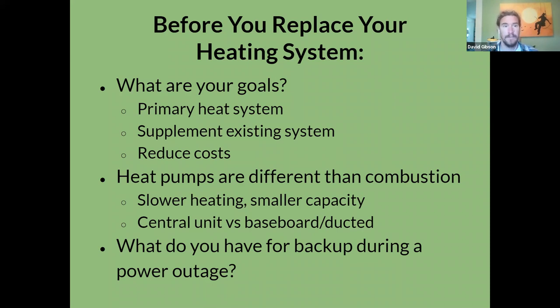It's kind of a different project if you're replacing your primary heat system versus adding something supplemental. Heat pumps work very differently than most combustion heating appliances. Most combustion systems, whether that's a boiler or a furnace, are designed to be able to reheat the entire space of the house very quickly. The thought being that if you come in on a cold day and your heat system has been turned down, you want to be able to bump up the thermostat and get it to 70 degrees in your house within 15 minutes. And heat pumps do not work that way.